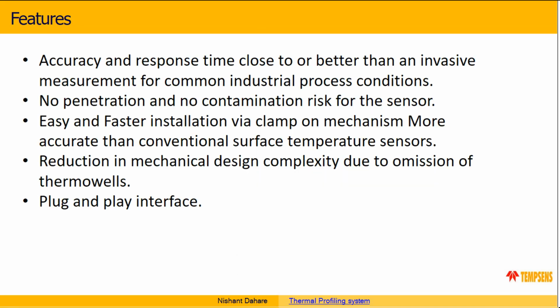So the major features of these clamp sensors are that the accuracy and response time are very close to the invasive type of thermowells, and even better than the invasive type of sensors, and much more accurate than surface temperature sensors. So plus or minus 2 degrees, without drilling any hole, you can measure the temperature. It's an easy and faster installation via clamps, so there is no need to drill. There is a reduction in mechanical design: you just screw the sensor tight and you can get the results. And it's plug and play: you just connect the USB to the software, and you get the exact readings of the fluid inside the pipe.